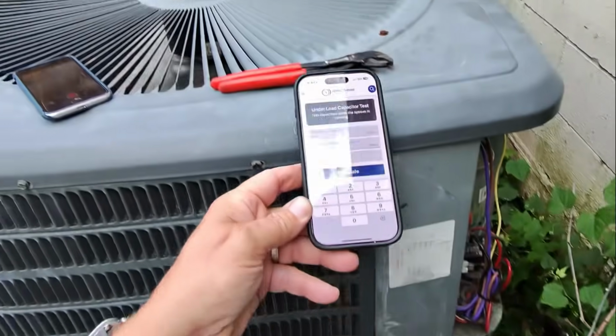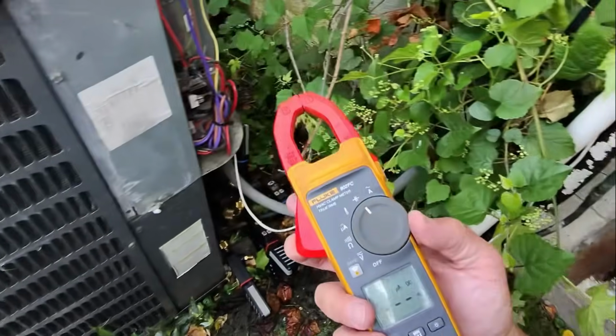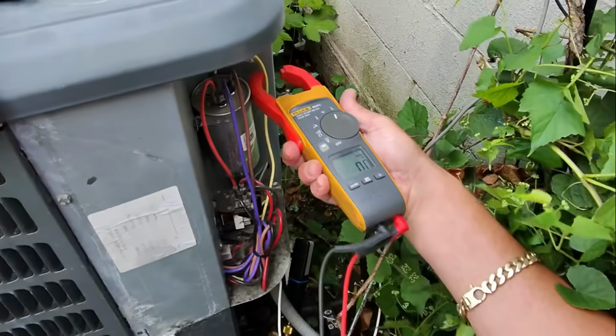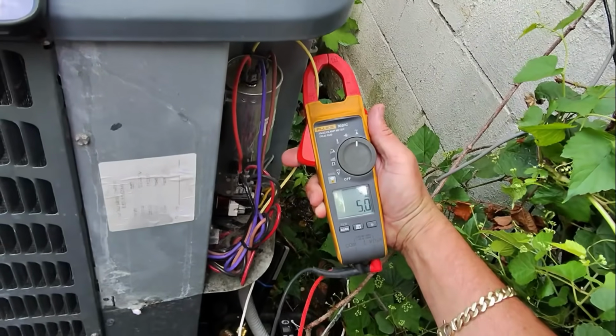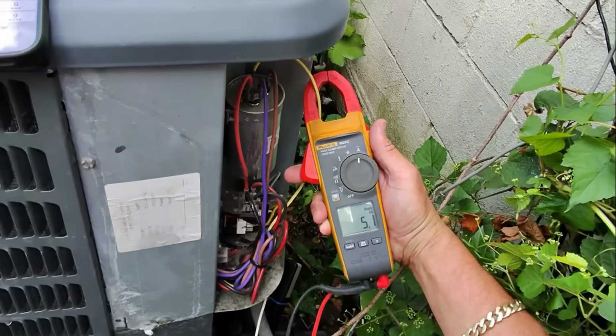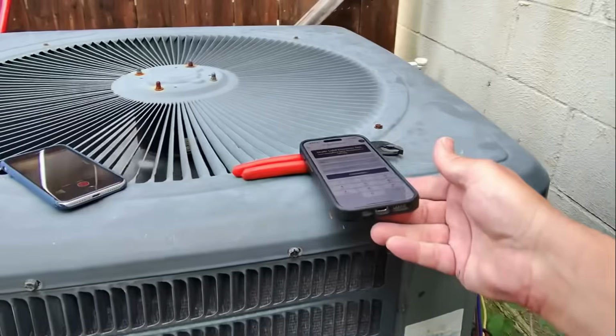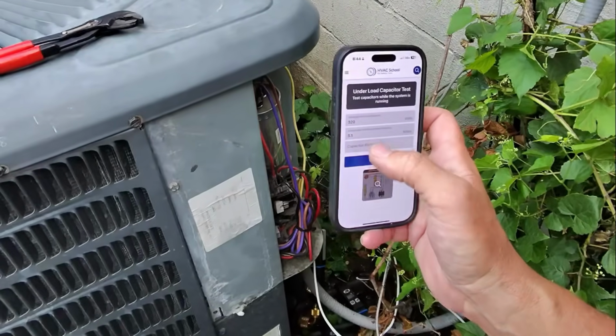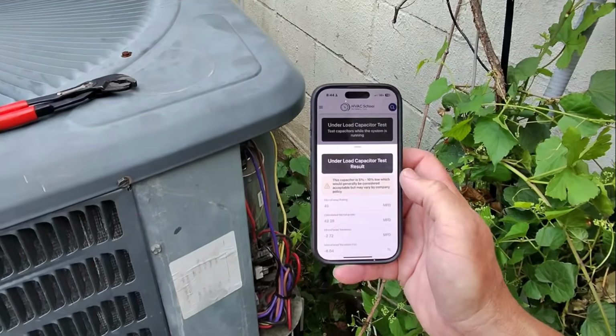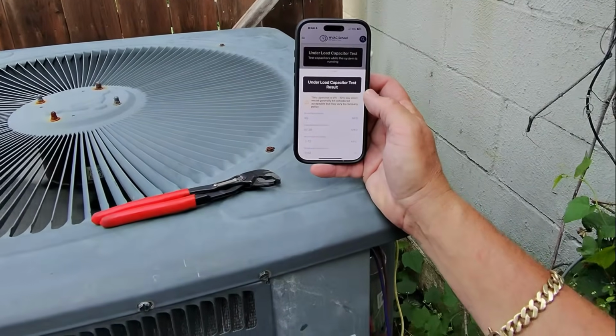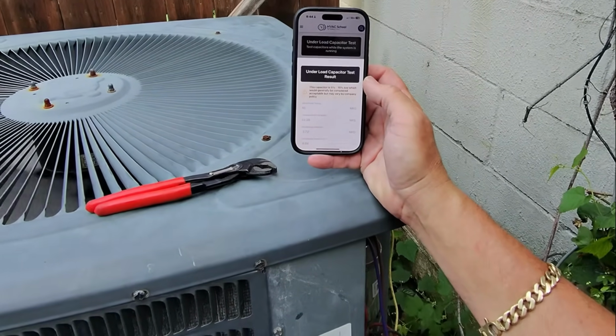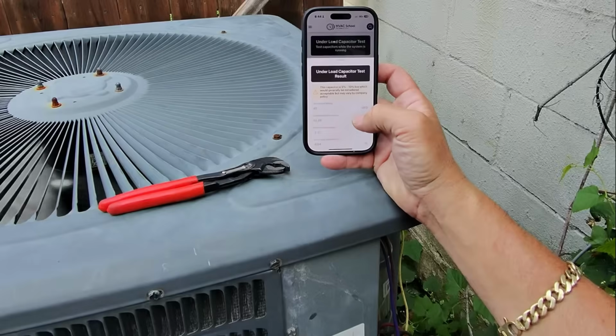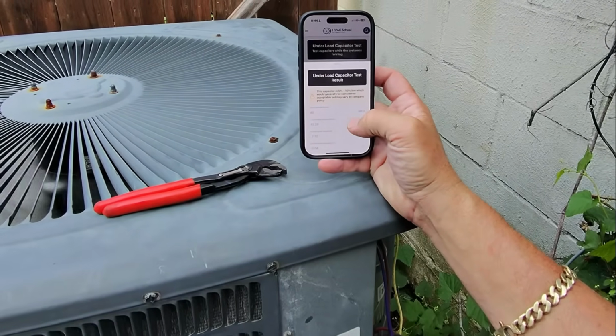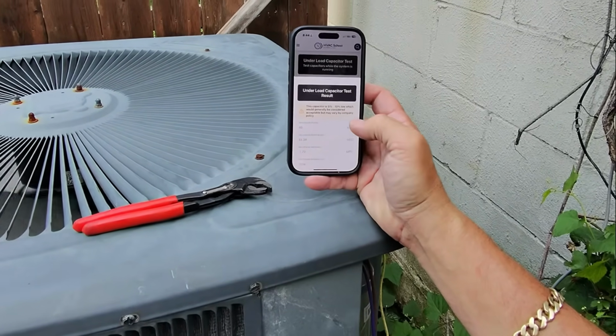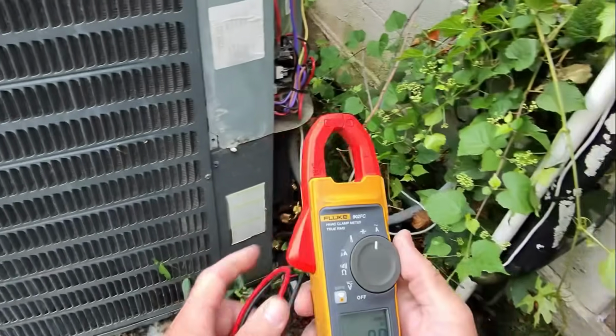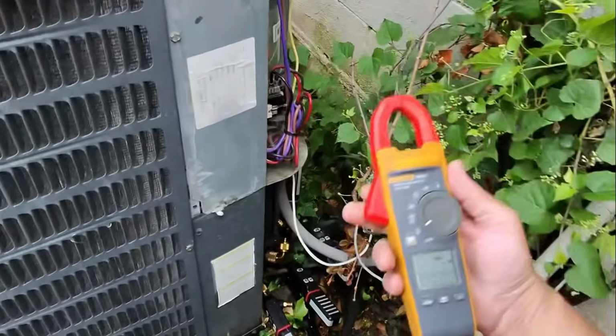We're going to take the amperage reading, take our clamp-on multimeter, set that to amperage, clip it onto that yellow wire. We're getting 5.1 amps. Let's type that in, 5.1, and this should be a 45. And we get, this capacitor is 5 to 10% low, which would generally be considered acceptable, but may vary by company. All right, we should be reading 45. We're getting 42.28. Let's check our voltage readings one more time.